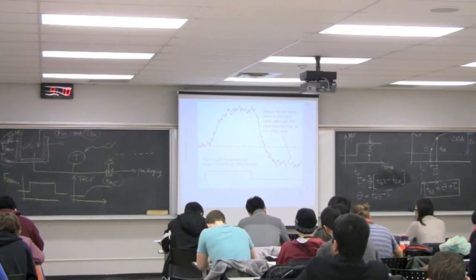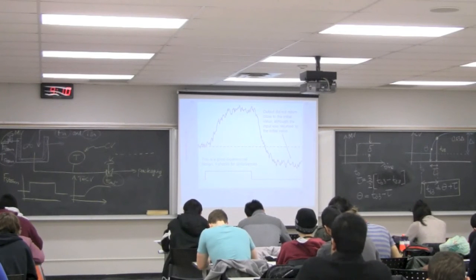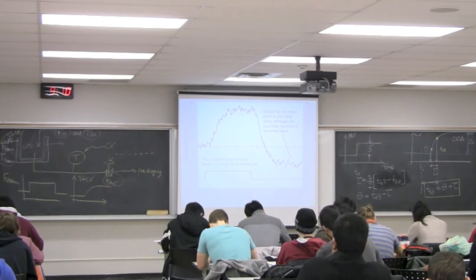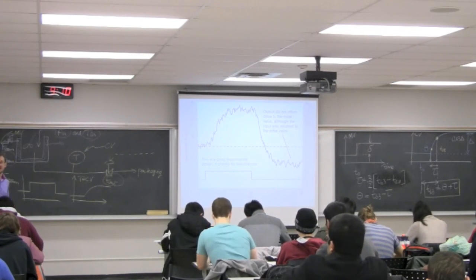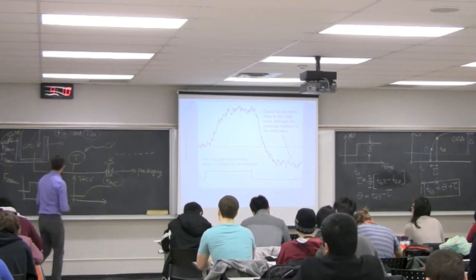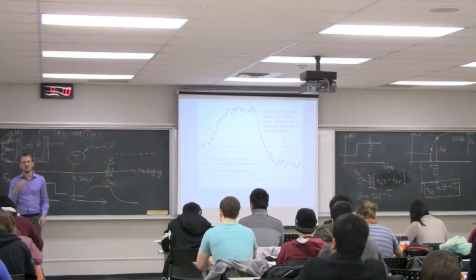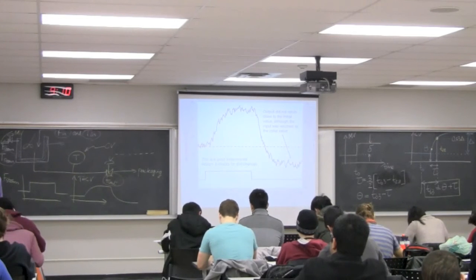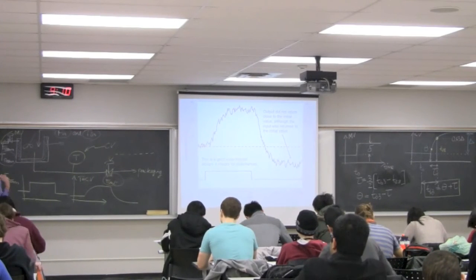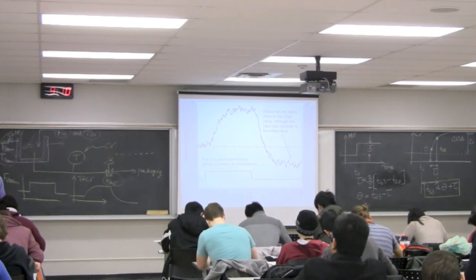I've got several disturbances in the system. When we're doing this test, remember we take that manipulated variable steam, F steam, and what we're going to say is change F steam in a step-like manner. And then observe this temperature over here. This T over there on the controlled variable will have some sort of delay and then it will start to rise. There will be some initial delay depending on the piping and how much it has to move through the jacket. There's going to be some delay before I see that ramp up in temperature. That's what this first half of the graph is. So up to time 40 minutes, things are going as planned. It drops down. I drop my steam flow rate back down now. And while I'm doing that, my disturbance hits me. And there could be any number of disturbances. For example, T in could have changed. F in could have changed. The temperature of the steam could have changed. This flow rate over here, the demand from the downstream line, the packaging could have changed. Any one of those red circle disturbances might have changed, causing the system to actually have a different behavior.